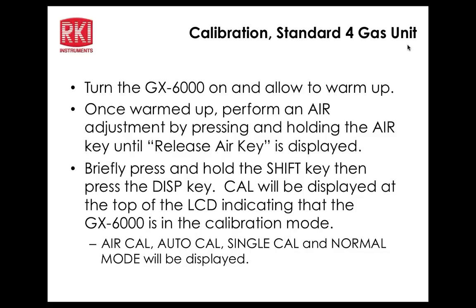Okay. And that's if you're doing a 4-gas calibration. So you could not put a 100% bottle of nitrogen on there and calibrate it down to 0? No, you can, but you have to do that in the single cal mode. Right. Okay, so you can still do that. Okay, got you. Yeah, if you're doing a single cal, you can set it pretty much anything less than 18. Right. Okay.